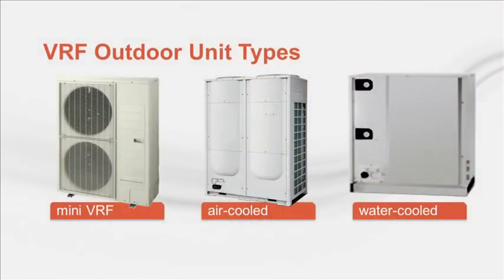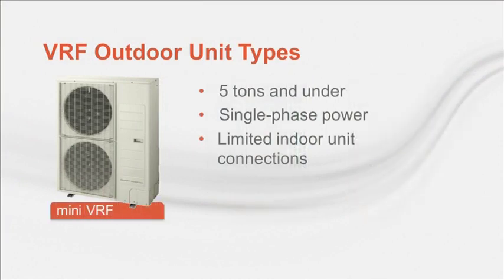Paul, can you take us deeper into system operation? Sure can, Eric. There are 3 basic types of outdoor units. At the small end of the VRF capacity scale are outdoor units 5 tons and under, commonly referred to as mini VRF. These models are typically available with single-phase power, making them suitable for residential applications. They are typically available as heat pumps and are only able to be connected to a small number of indoor units. They cannot be combined to form larger capacity outdoor systems.